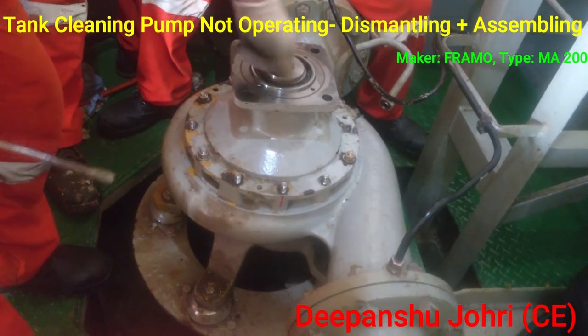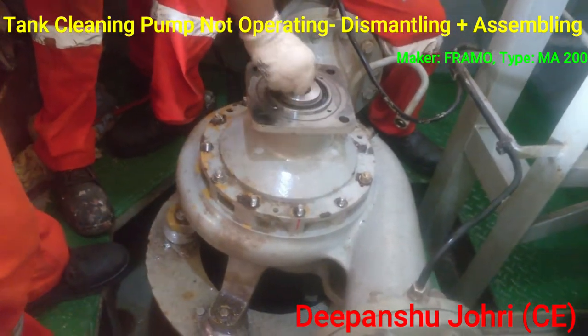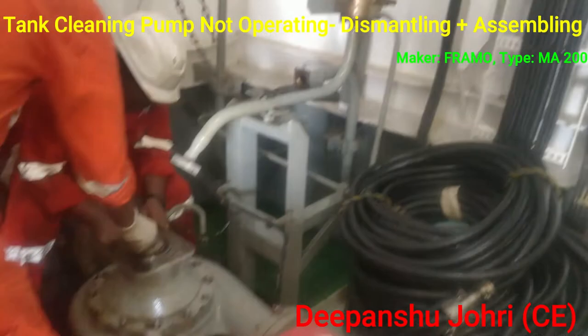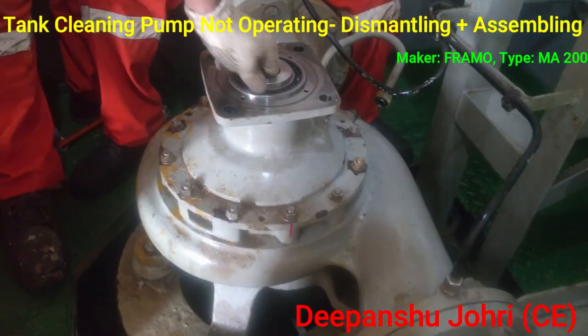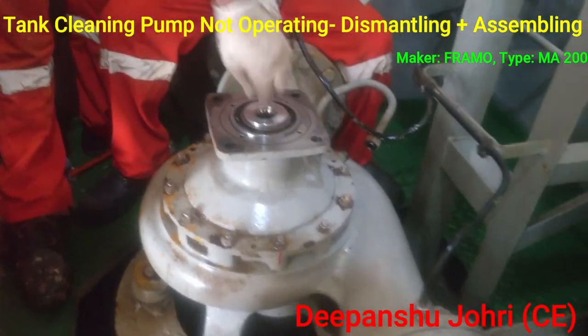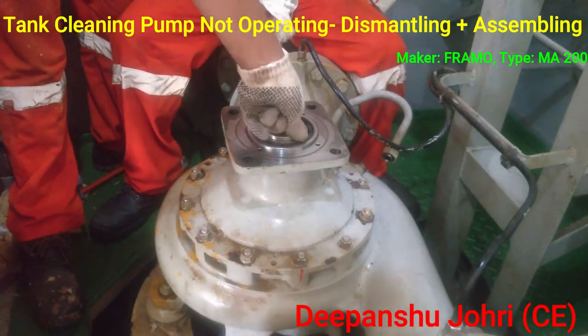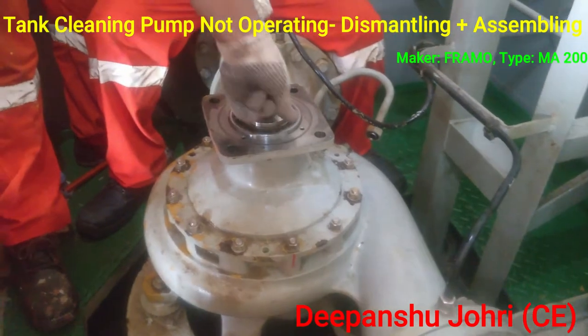Four bolts have been fitted so far. Let us fix the other parts and then check how it works. After all bolts are in, it is again rotating clockwise and anti-clockwise — all bolts are tight. This confirms there is no problem with the mechanical side. Before dismantling it, this rotation check was not done — it was removed separately without this prior check.